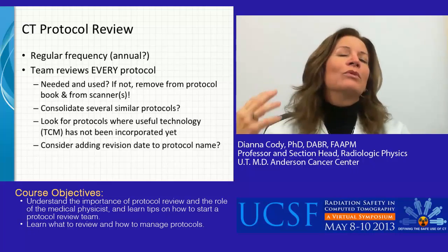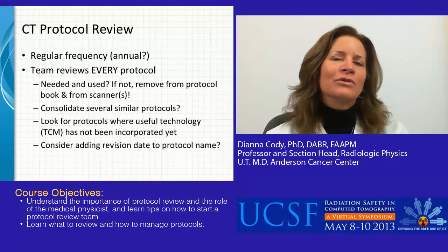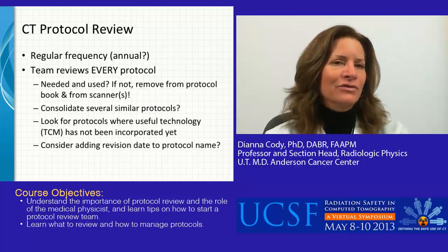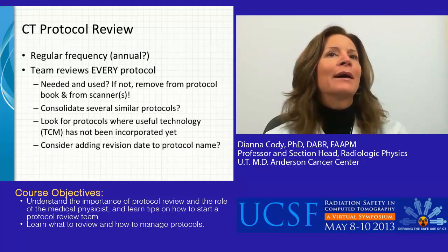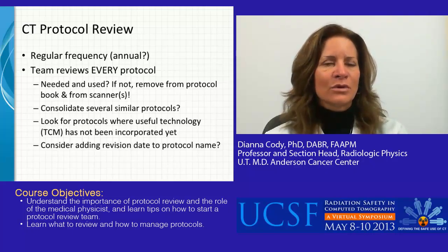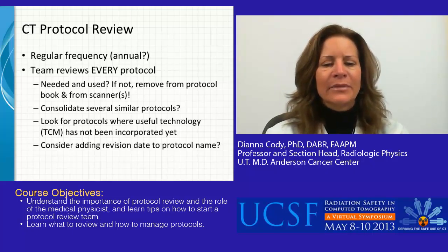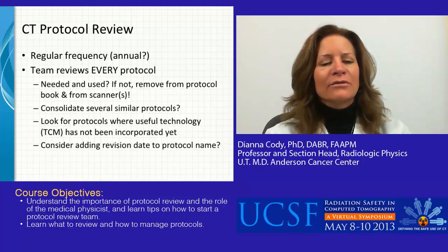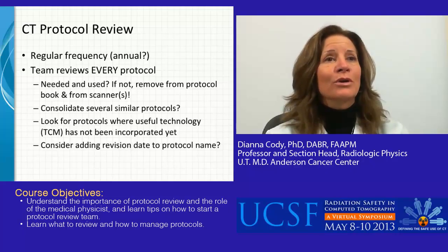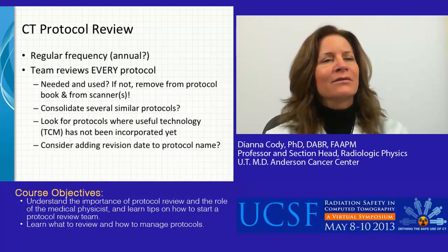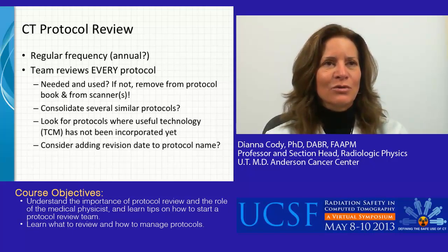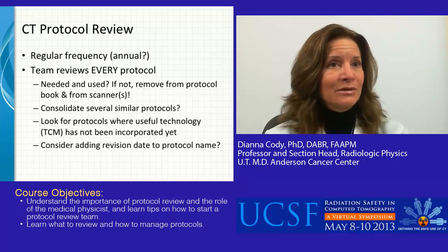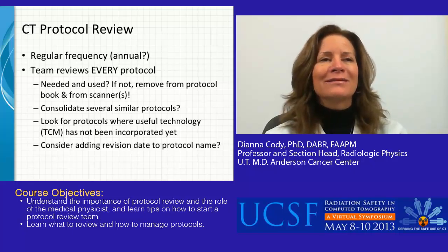While you're in this review process, look for opportunities to consolidate protocols. Do you really need 5 different flavors of this one protocol? Can't we combine them all into a single protocol and get what we need? You want to look for those protocols where useful new technology such as tube current modulation has not been incorporated yet. You may be surprised at the number of instances where that hasn't happened, where it makes perfect sense, but no one has yet gotten around to it.